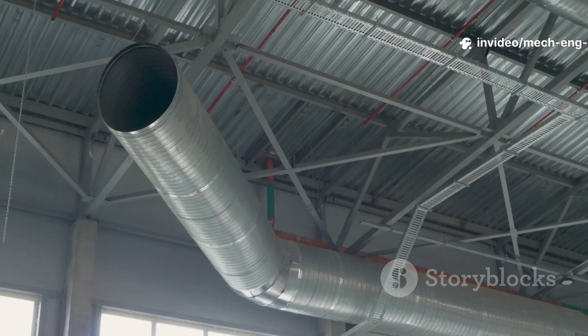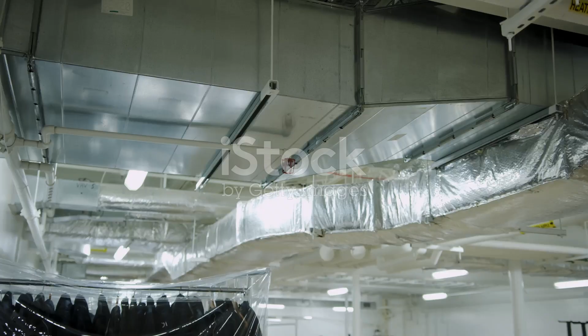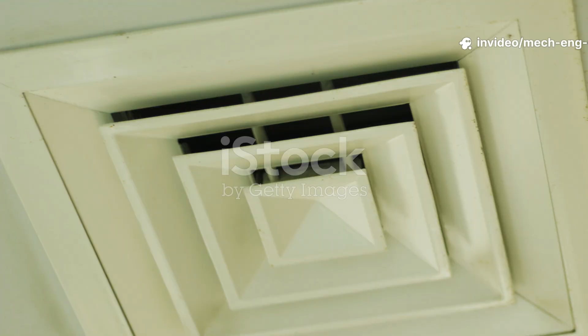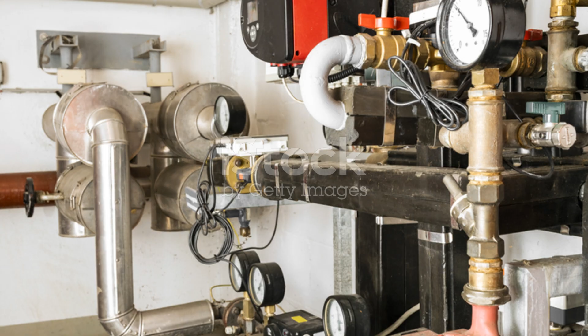The Air Handling Unit, AHU, supplies conditioned air at a nearly constant temperature, typically 12 to 13 degrees Celsius. The air flows through ducts to multiple VAV boxes, each serving a zone or room. Each VAV box has a damper that adjusts to control how much air enters that zone. A thermostat in each zone measures temperature and sends a signal to the VAV box to increase or decrease airflow. When the cooling load decreases, the damper closes partially, saving fan energy and reducing system demand.